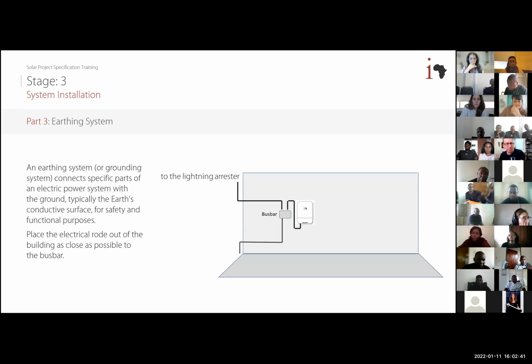Last thing to install is an earthing system and a lightning arrestor on the roof. The lightning arrestor should be connected to the earthing, and that connection should be as close as possible to the room with the energy box - hopefully on the outside wall of the energy box. You use a rod, bury it in the ground with cement, and connect the lightning arrestor to it using a bus bar.